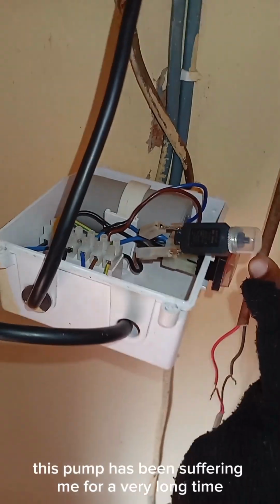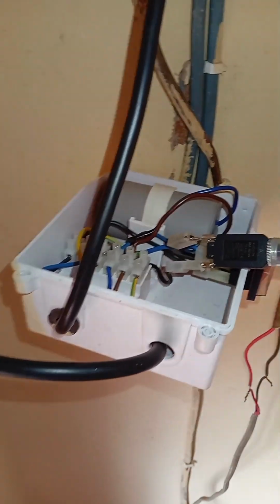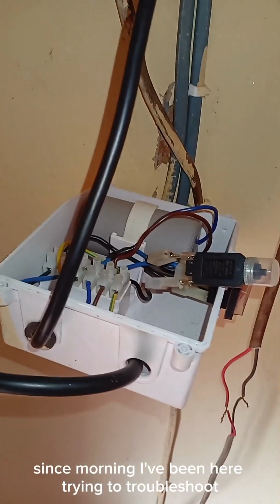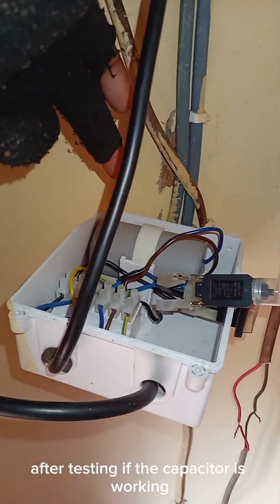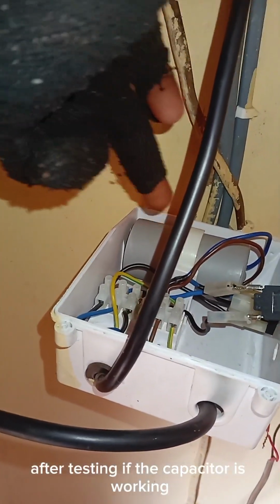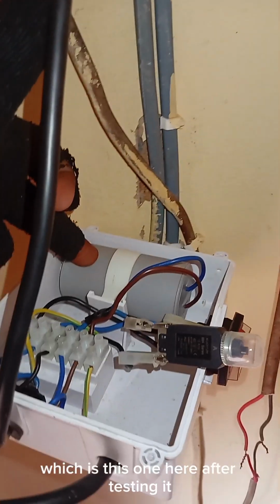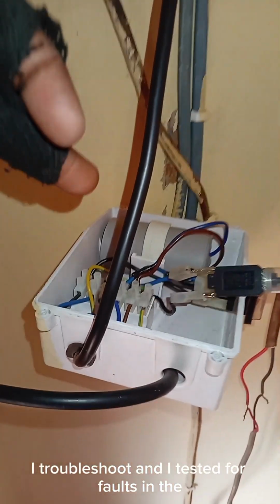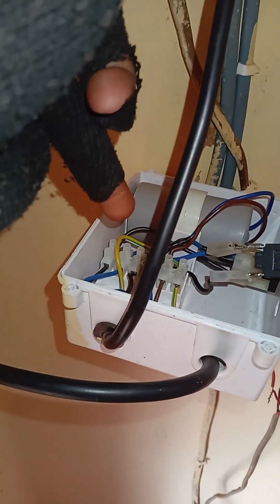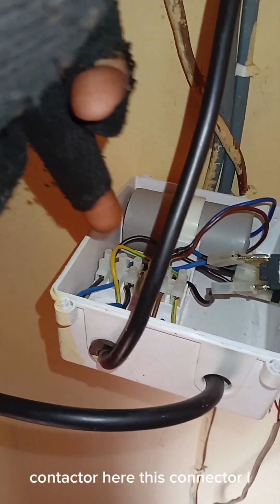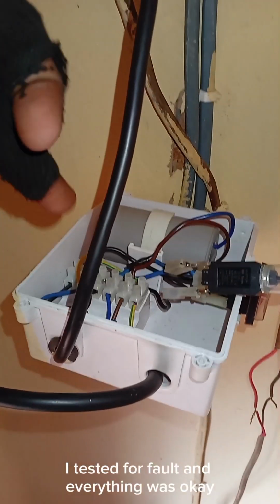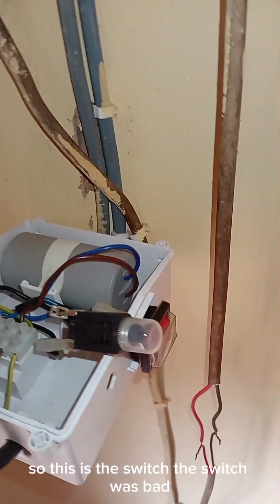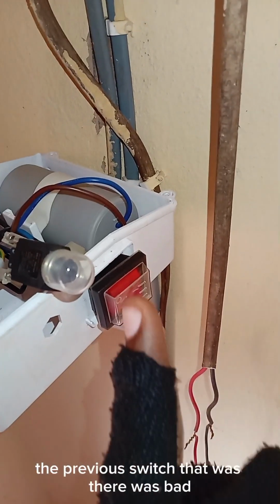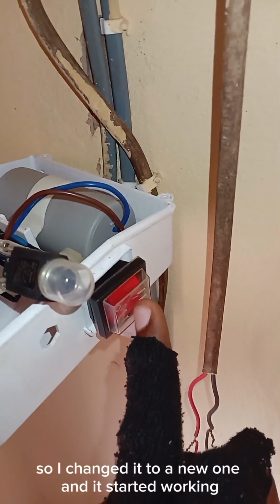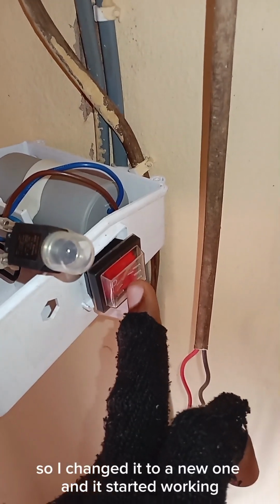So this pump has been suffering me for a very long time. Since morning I've been here trying to troubleshoot. I tested if the capacitor, which is this one here, was working, and it was working. I tested for faults in the contactor here, and everything was okay. So the switch was bad. The previous switch that was there was bad, so I changed it to a new one and it started working.